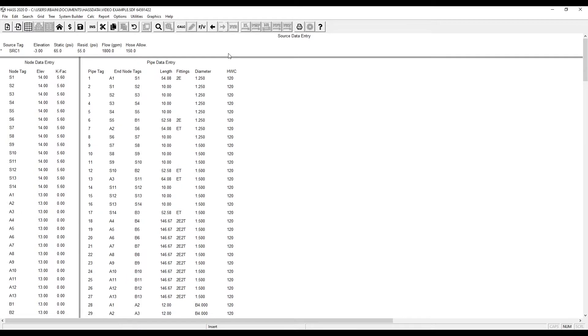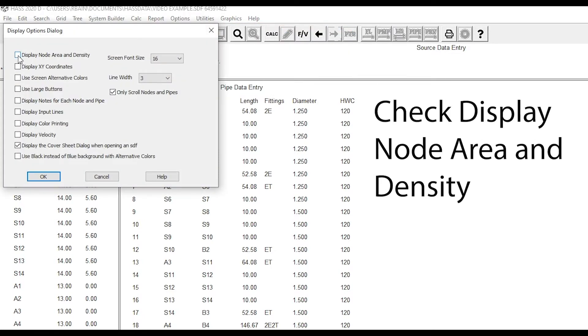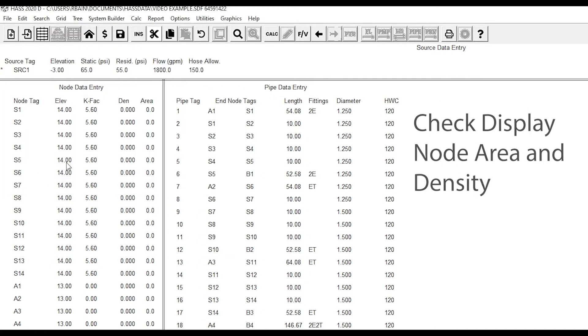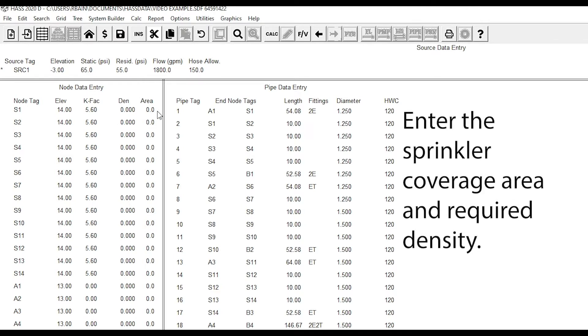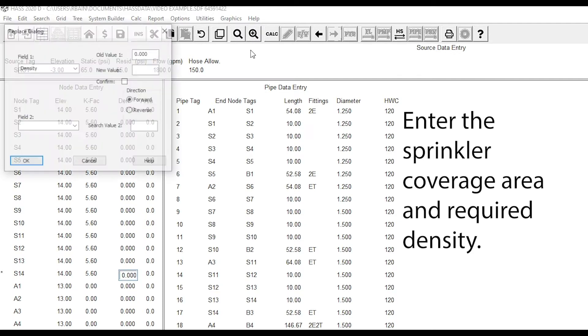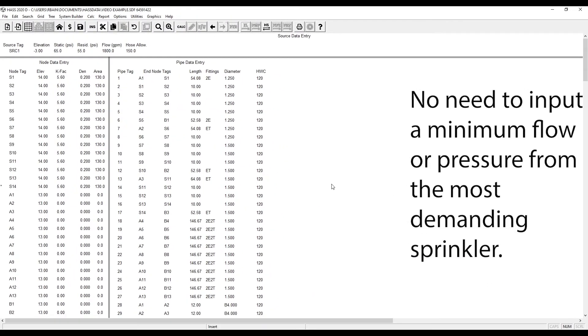Welcome back to another tech tip. Did you know that HASS can calculate the minimum pressure or flow for your sprinkler? Start by going to Options, Edit Options, Display Options, and select Display Node Area and Density. Now, instead of having to calculate your minimum pressure or flow, all you have to do is enter your coverage area and your density — HASS will take care of the rest for you.